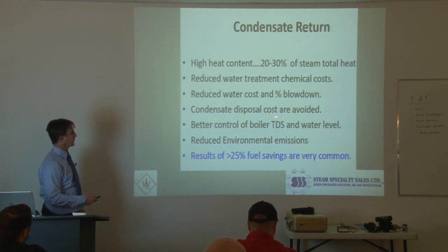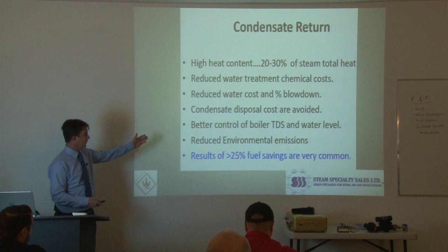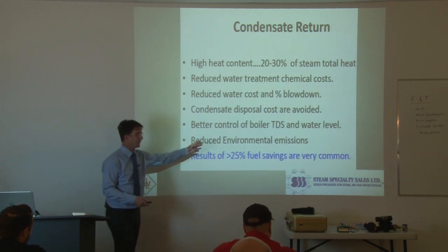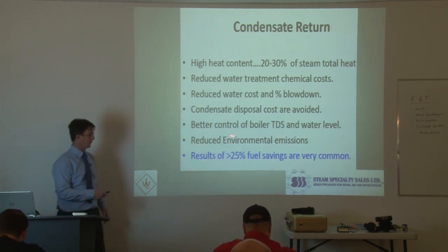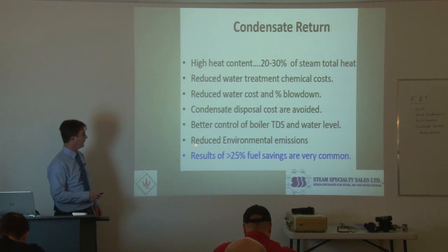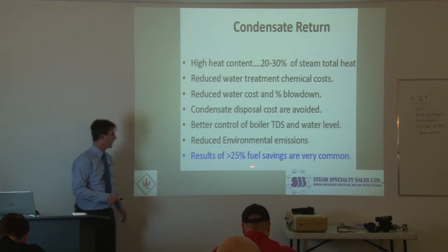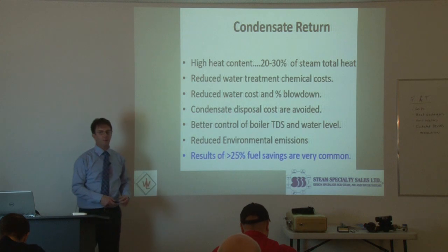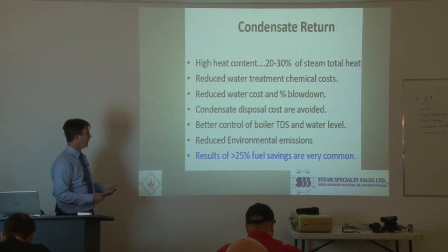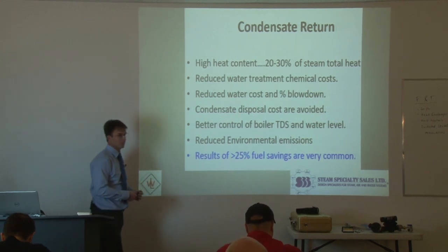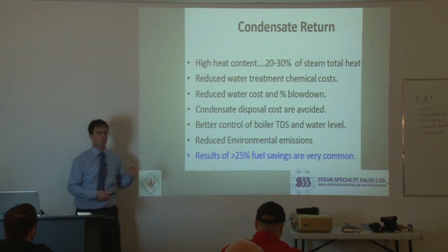Condensate disposal costs are avoided. We get better control of TDS - total dissolved solids - in a boiler, and better control of the water level in a boiler. There are also reduced environmental emissions and increased fuel savings. So returning condensate back to the system helps us save energy and save other costs.